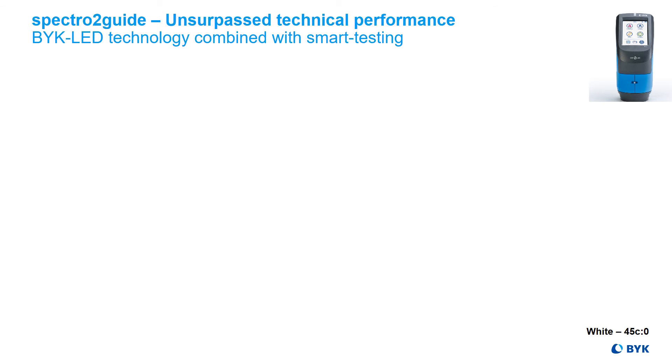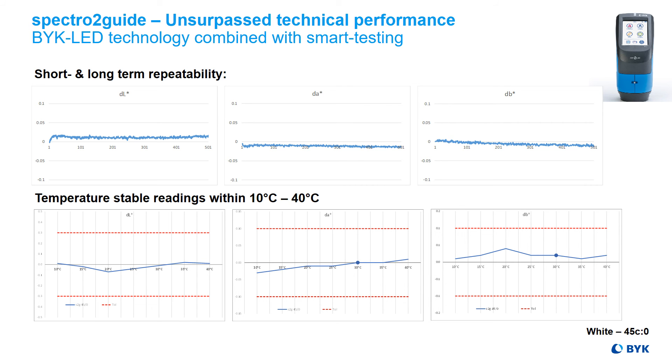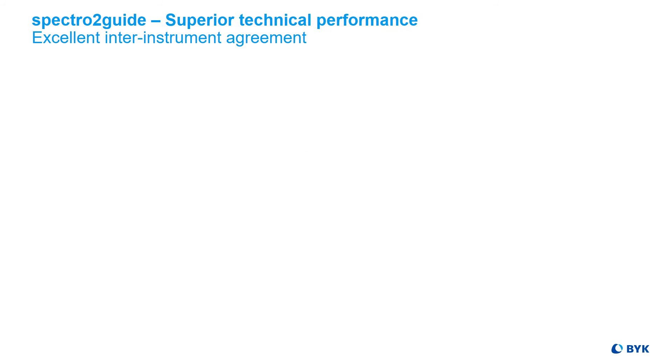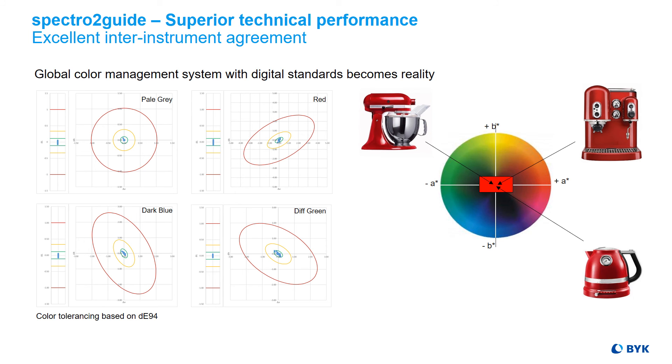The spectro2guide offers you an unsurpassed technical performance due to our high-tech LED technology combined with smart testing of optics and electronics. We guarantee an excellent repeatability, temperature-stable readings within 10 to 40 degrees Celsius, and an outstanding inter-instrument agreement. Thus, a global color management system with digital standards becomes reality without special close tolerance adjustments needed.